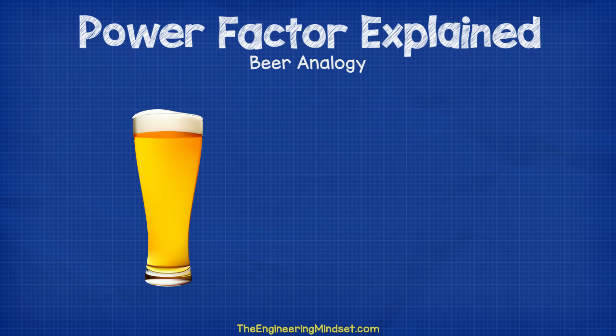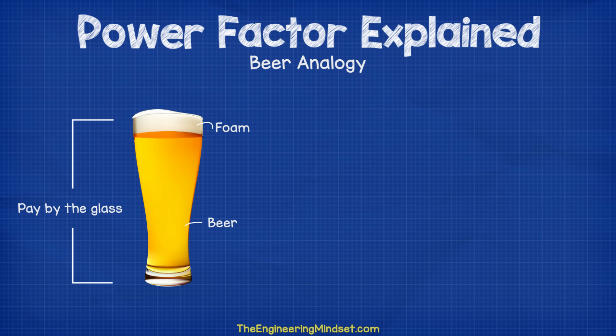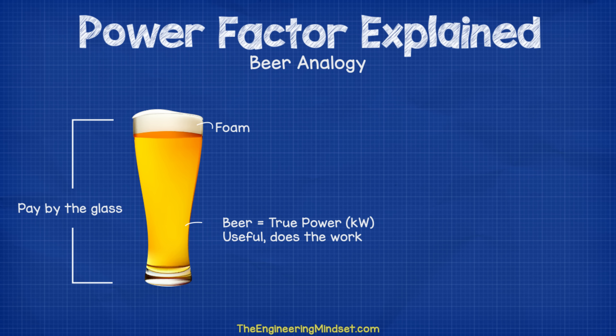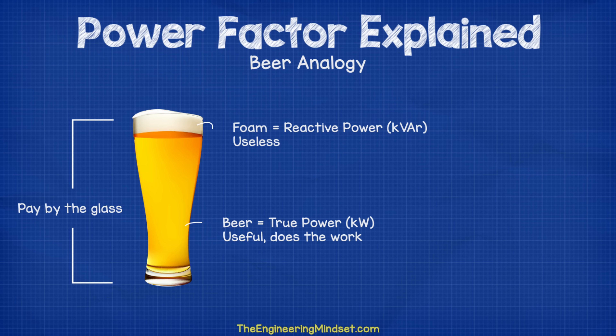My favorite analogy to explain this is the beer analogy. We pay for beer by the glass, but inside the glass there is both beer and foam. The more beer we have, the less foam there will be, so we get very good value for money. If there is a lot of foam, then there's not a lot of beer, and so we're not getting very good value for money. The beer represents our true power, or our KW, our kilowatts — this is the useful stuff we want and need; this is what does the work. The foam represents our reactive power, or our KVAR, kilovolt amps reactives. This is the useless stuff — there will always be some, we have to pay for it, we can't use it, so we don't really want much of it. It does actually have a use and a purpose, but we'll see why later in the video.